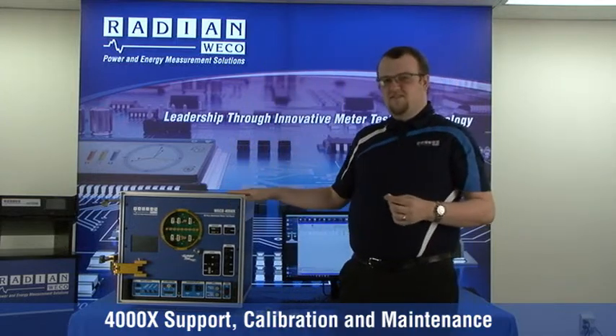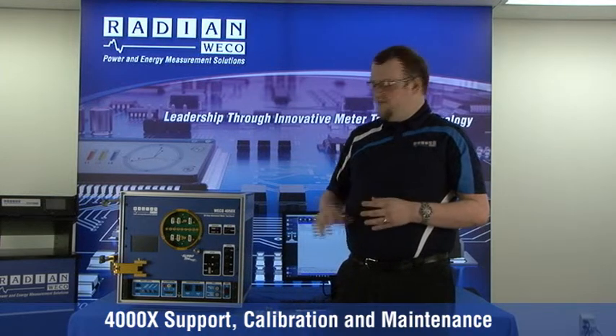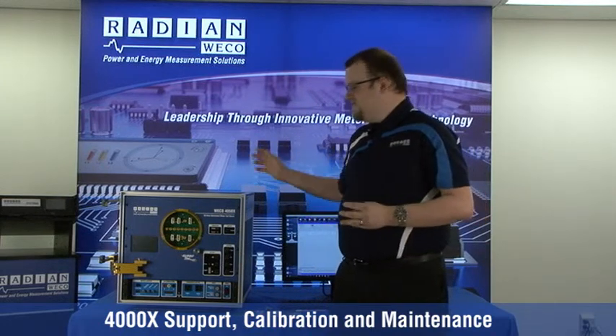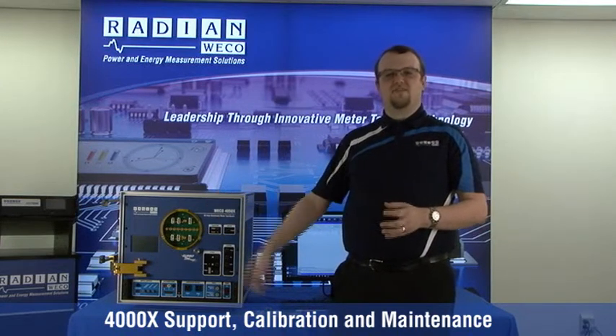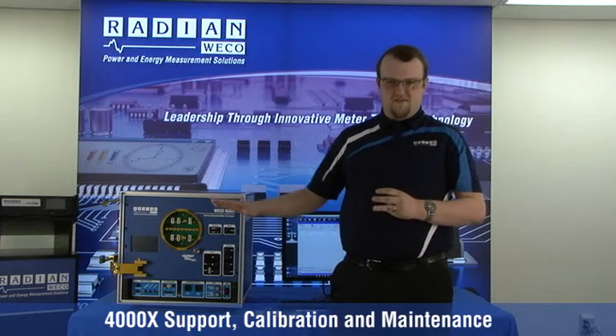Every so often, the test board may need internal cleaning and dust removal. To remove dust internally from the test board, remove the 8 screws holding the front panel onto the frame. Open the back door of the 4000X as well. Using a low pressure air source, remove any dust or accumulation inside of the test board. Wipe down any remaining dirty surfaces with a non-abrasive cloth. When you are done cleaning the inside, close the back door and reattach the front panel.